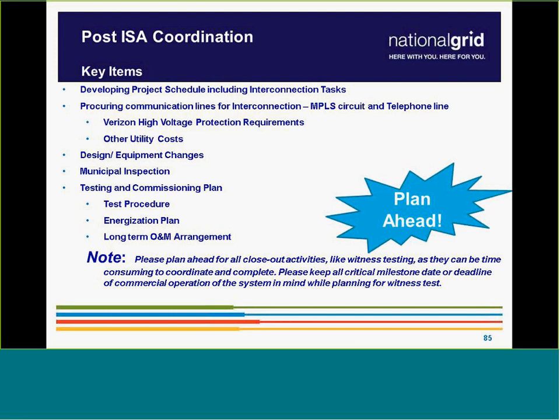So just make sure that municipal inspection is called in. Some customers submit all the documents, everything is reviewed, construction is complete, and then the day of the witness test, we find out that the inspector never called and cleared the municipal inspection. So there is this document called certificate of completion where the wiring inspector signs off on it and dates it, right? That's one of the responsibilities that he has to do with us.